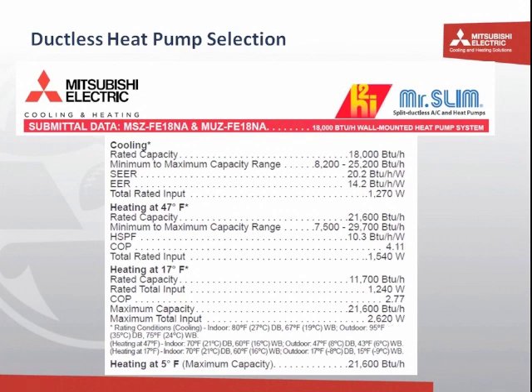But again, the COP is 2.77. So for every watt of input to the system, we're getting 2.77 watts of heat into the space. So still a far more efficient way to do it than a resistance or supplemental heat strip. And then all the way down at 5 degrees, again with the hyperheat feature engaged, we're still producing that full rated capacity, and will continue to do so even as the system drops into the 0 and below, although it will taper off slightly. So this is the general overview of capacity and watt inputs.